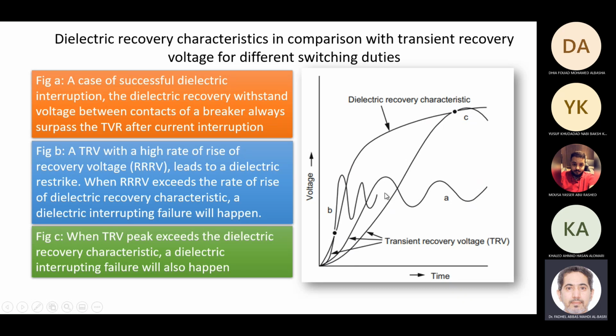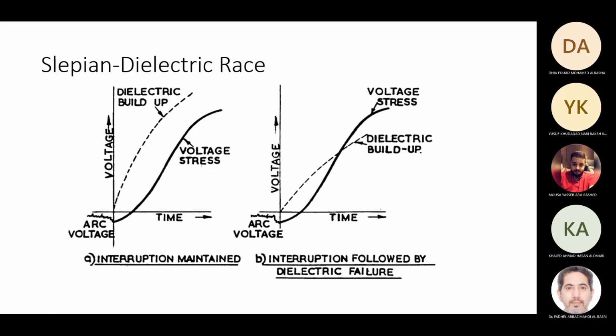And the third here, initially the breaker looks like the dielectric strength voltage is more, but at this point the voltage across the contacts becomes higher than the dielectric strength, so there will be an arc reignite again. So for this theory, the dielectric should retain its recovery very quickly and faster than the transient recovery voltage for the successful clearing of the arc. So this is the voltage across contacts, and this is the dielectric build up across the medium of the oil, for example.